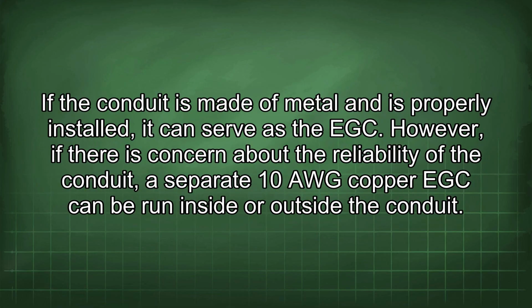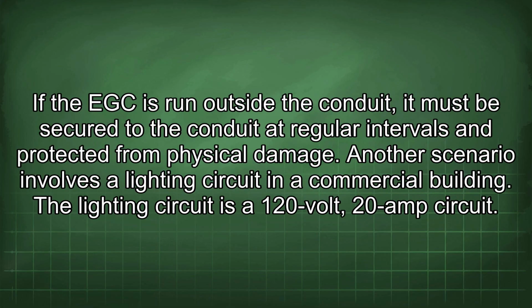If the conduit is made of metal and is properly installed, it can serve as the EGC. However, if there is concern about the reliability of the conduit, a separate 10 AWG copper EGC can be run inside or outside the conduit. If the EGC is run outside the conduit, it must be secured to the conduit at regular intervals and protected from physical damage.